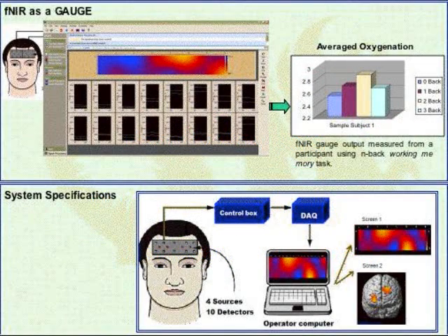The device uses near-infrared light LEDs to shine light through the skull and into the brain while the test subject is actively involved in cognitive activity. The light is absorbed by any hemoglobin present in the brain, and the light that is not absorbed is reflected back to the receiver diodes. This signal can be translated by software into an image that shows the amount of hemoglobin in the brain.